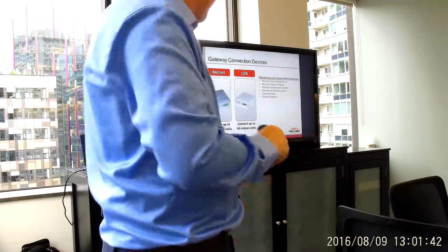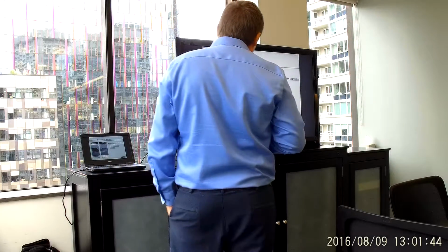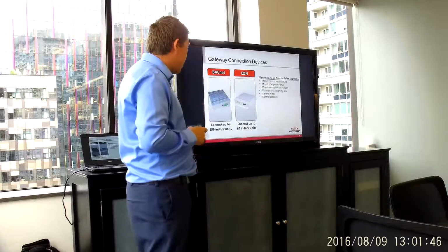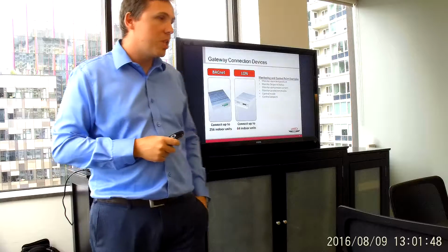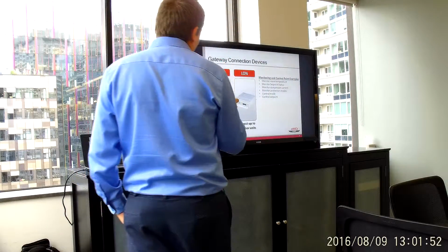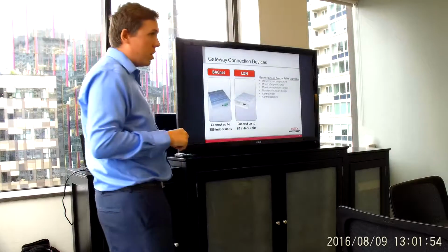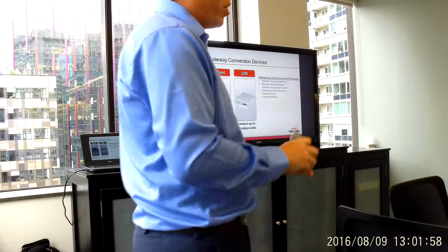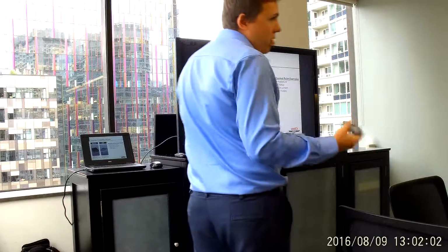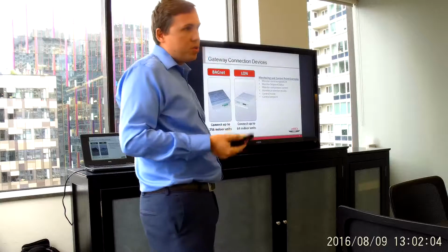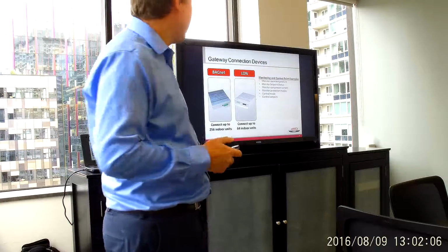Now gateways, we're almost done. BACnet and LonWorks, these are the two different output gateways we've got. We don't just have monitoring, we have control mode and set point control. I can also see room temperature, operating position, and error codes, and feed that back out again. So it operates like a BACnet system. Very straightforward, I don't need to go into much detail.